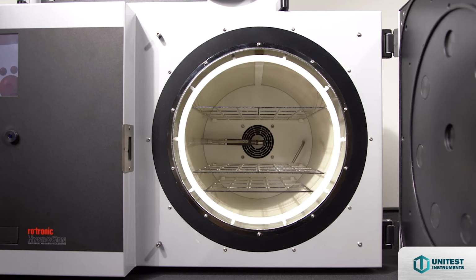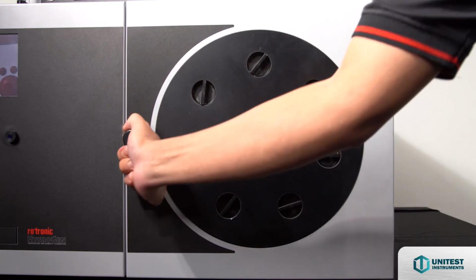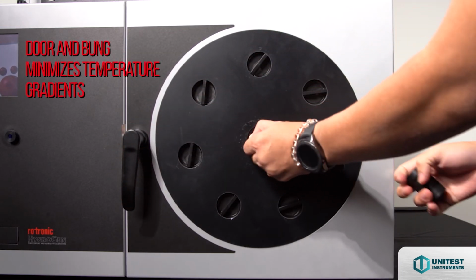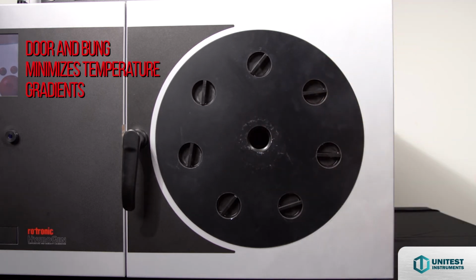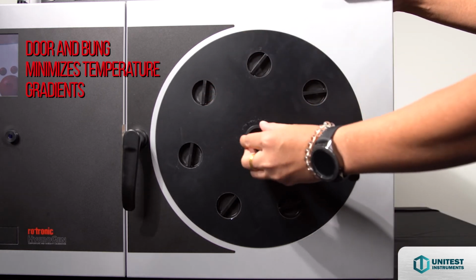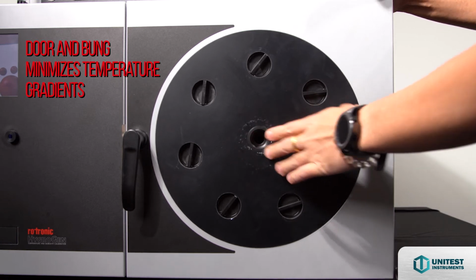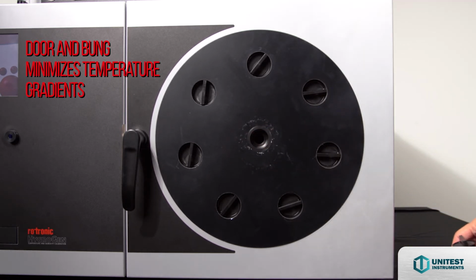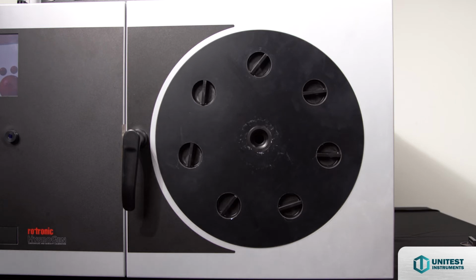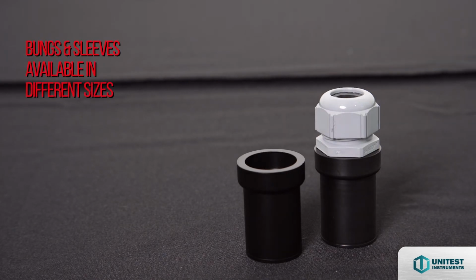The HG2 door and bungs play a key component in the operation of the generator. A well-designed door minimizes temperature gradients within the chamber to provide uniformity when readings are measured. Rotronic has taken special considerations when designing the overall insulation for the HG2. As such, even the bungs or sleeve, where the probes are inserted into the chamber, are insulated. There are also different models of bungs available that cater to different probe sizes, providing precise probe connection ports to eliminate leaks and losses.